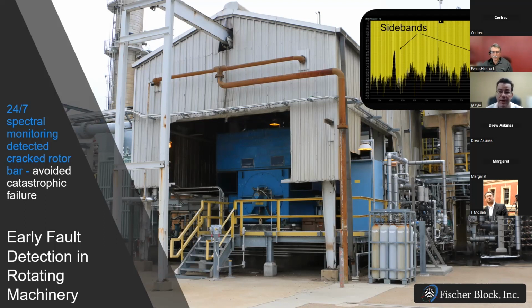And those sidebands will actually grow in height. And as those joints degrade, if the height of those sidebands finally hits a threshold, it becomes like a yellow versus a green, and then it becomes red. And then we alert the operators through the dashboard or even email or however they have set up their alert notifications. And what's important here also is the noise floor. The more dynamic range your system has, so a system like ours that can sense very subtle changes or distortions as compared to the main signal, that's what determines the noise floor. And so if the noise floor is low, then you can see these sidebands begin to grow much earlier. You get many more weeks and months notice before you have to plan an inspection. And so we're proud of the noise floor we have, 100 dB range. We've seen other systems at 60 dB, so we provide a number of months additional notice to our customer base.